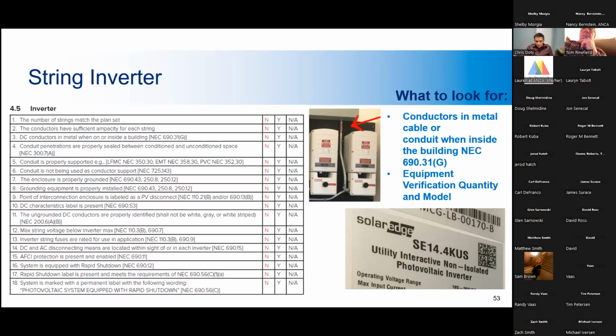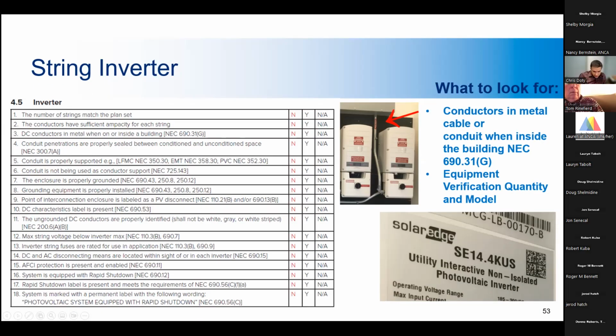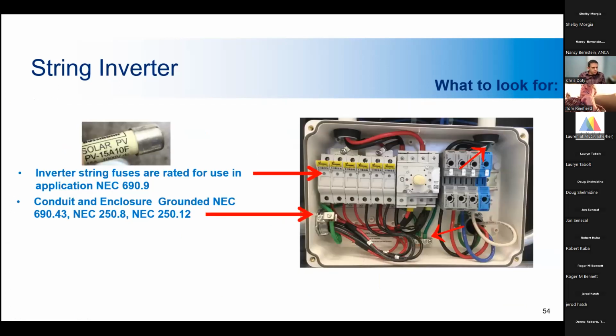In this case right here, the DC conductors are coming down from this junction box up here, which comes from the roof. You have to verify that they're in metal conduit, because all DC conductors are supposed to be in metal conduit. And they have to be labeled every 10 feet, showing that DC conductors are inside that conduit. The metal conduit provides an additional barrier in case of an emergency, so that anyone in the vicinity will not have contact with the DC wiring. And all the conduit has to be properly bonded to the grounding system. And I think that's about it for that one.